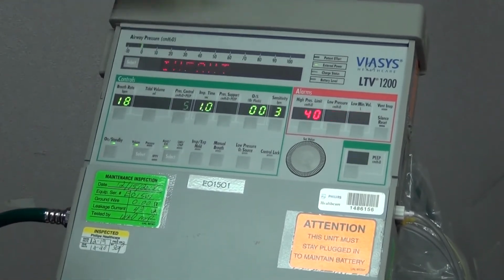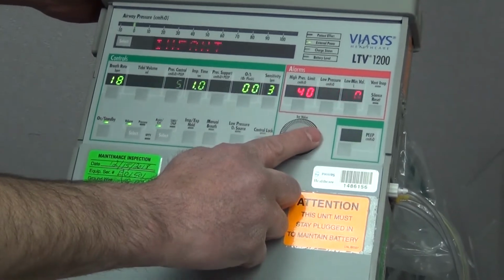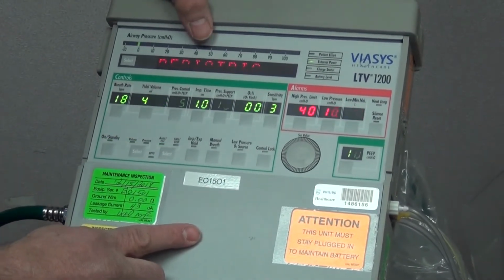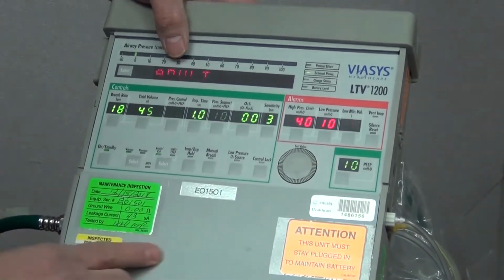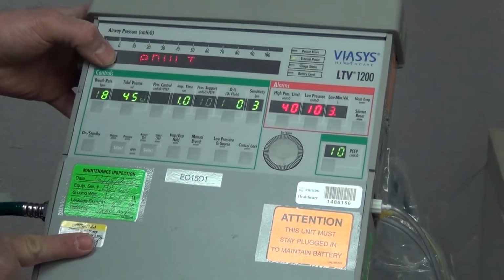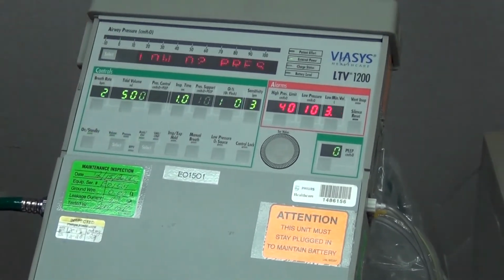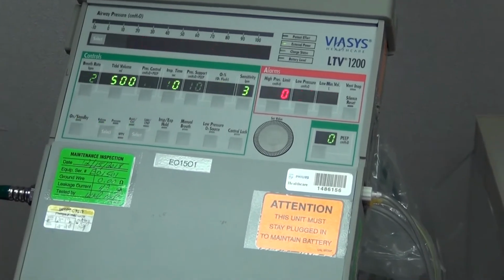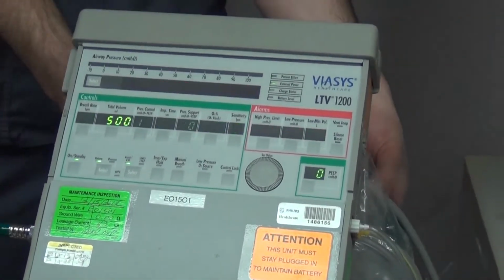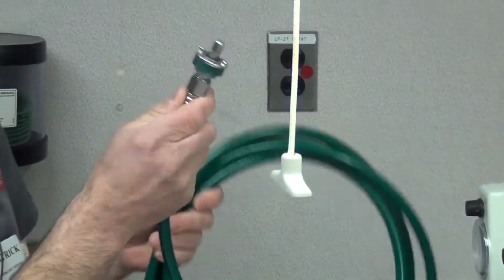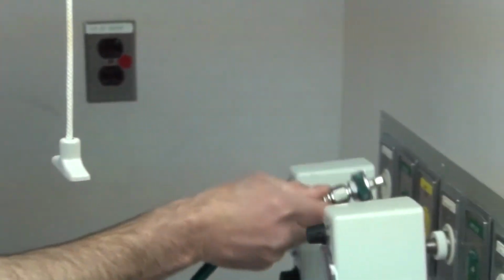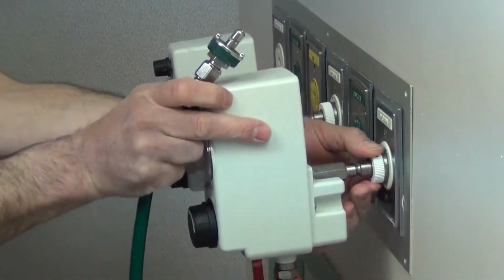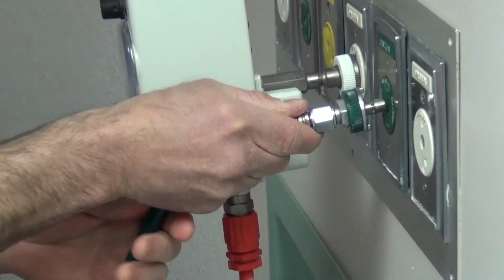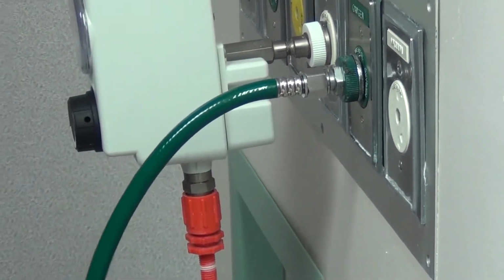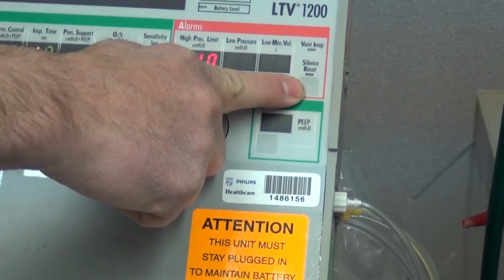Next menu. Is this an infant? No, it's not. So I'm going to turn this. Is it a pediatric patient? Nope. I'm going to keep turning it. We are going to select an adult patient. And we're going to hit the select button again. Notice it says low O2 pressure. Oh yeah, we have to connect our oxygen. Here it is. And again, like in our previous video on the other ventilator, we're going to plug it into our wall outlet here, which let me remove, and we're just going to plug it in. And there it goes. We go back to our ventilator. Do we want to keep the alarm going? No. We're going to hit the silence button right over here.